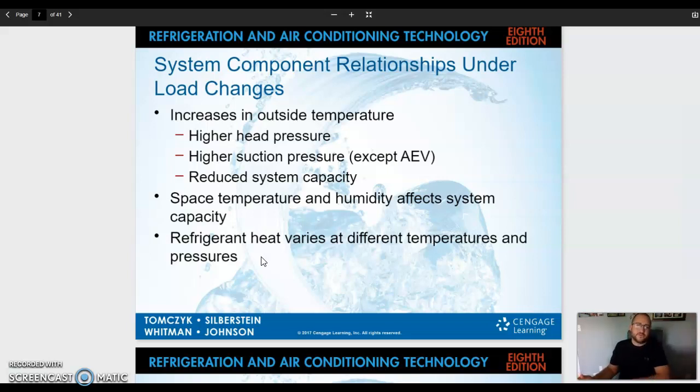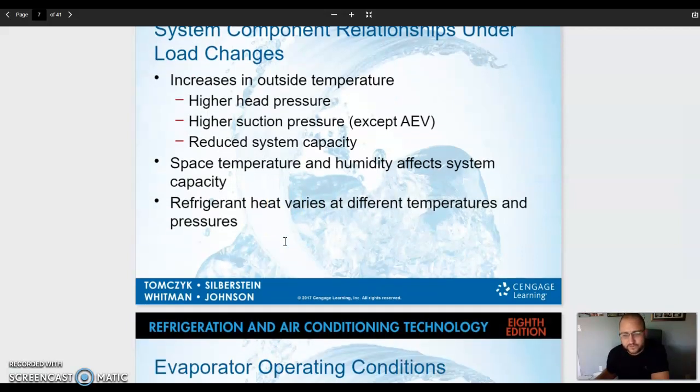That's where some of your efficiency comes from. Newer systems will use larger coils, which allows it to move the same amount of heat over a greater surface area, which keeps its pressure down, which keeps the pressure on the compressor down, which keeps the amperage down, which reduces your electrical usage. So in a nutshell, that's one reason why some of the more efficient systems have huge oversized coils, so they can move it easier without raising the pressure so high.